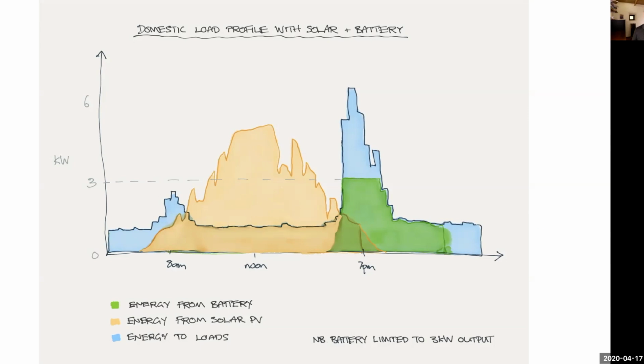And so you'll see, if you model a lot of homes, including my own, in the morning you'll see all these little spikes: the coffee machine, the toaster, the dishwasher, they just spike, spike, spike. And they can be coincidental spikes, particularly natural coincidences, like anything that washes or heats water is probably going to run a pump if you've got a pressure pump. So they both come on together. Now, those peaks are going to be delivered by your inverter system. So both your battery and your inverter need to be sized to deliver that peak demand, and your PV system needs to be sized to give the energy requirement over the whole day.